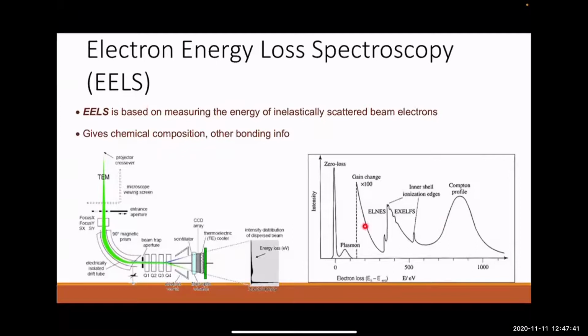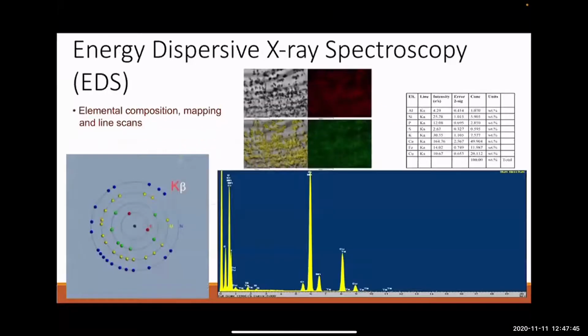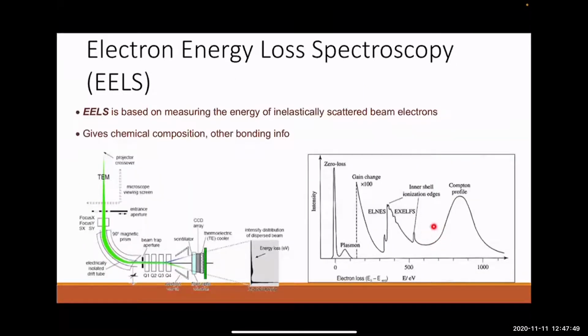So you can get a spectrum in some ways very similar to what I showed before with the EDS, where you're measuring the energy of X-rays. Here you're measuring how much energy the electrons have lost if they've scattered through the material. And while it can give you similar information to EDS, it can give you much more information as well. There's very complicated analysis, EXELFS, extended energy loss fine structure, and near-edge structure. It's complicated, but it can give you more information on things like oxidation states, Fermi densities, things like that. So it's quite a powerful technique in its own right. And you can do that on a TEM that's equipped with an EELS spectrometer. An EELS spectrometer is basically a way to take the electrons and disperse them according to their energy so you can get the spectrum. So very useful technique.